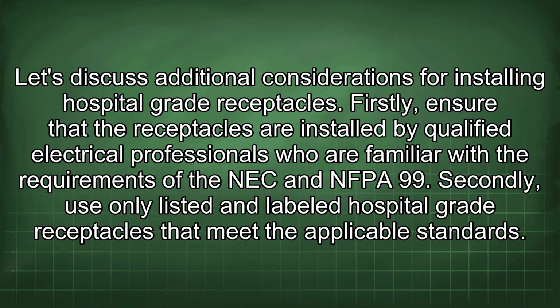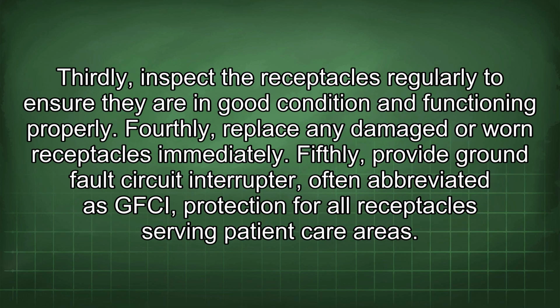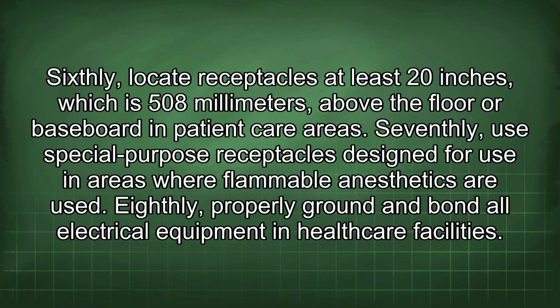Firstly, ensure that the receptacles are installed by qualified electrical professionals who are familiar with the requirements of the NEC and NFPA 99. Secondly, use only listed and labeled hospital-grade receptacles that meet the applicable standards. Thirdly, inspect the receptacles regularly to ensure they are in good condition and functioning properly. Fourthly, replace any damaged or worn receptacles immediately. Fifthly, provide ground fault circuit interrupter, often abbreviated as GFCI, protection for all receptacles serving patient care areas. Sixthly, locate receptacles at least 20 inches, which is 508 mm, above the floor or baseboard in patient care areas.